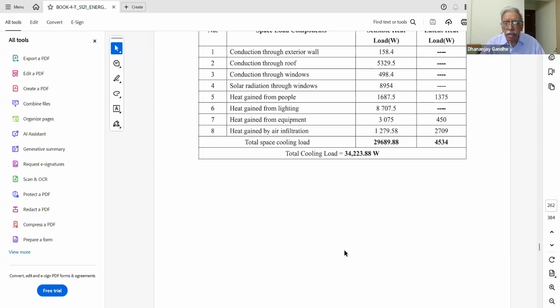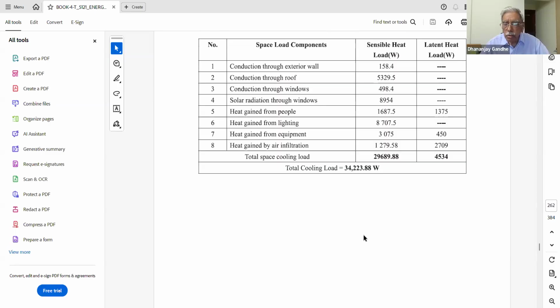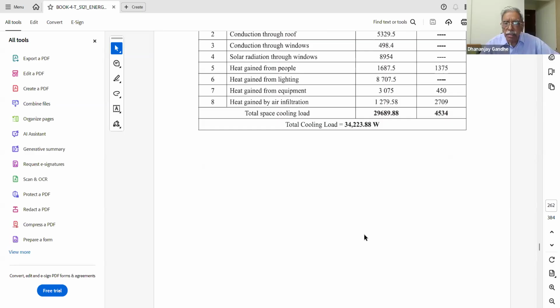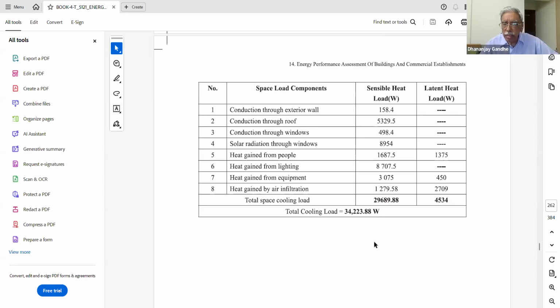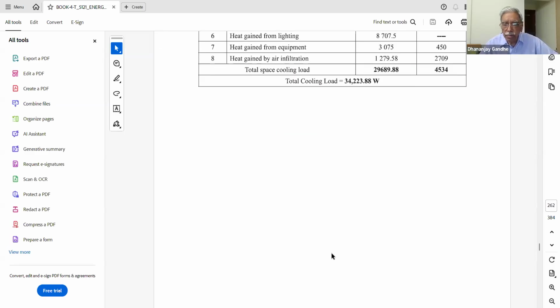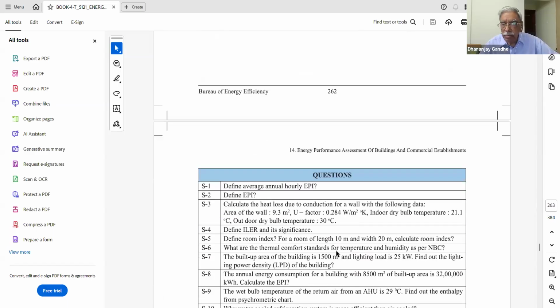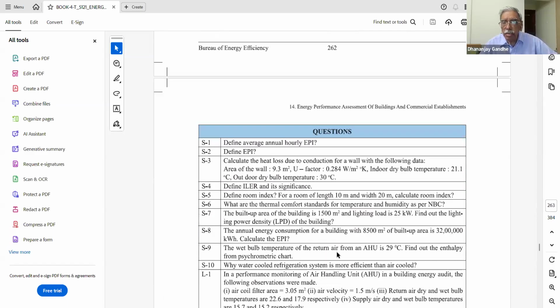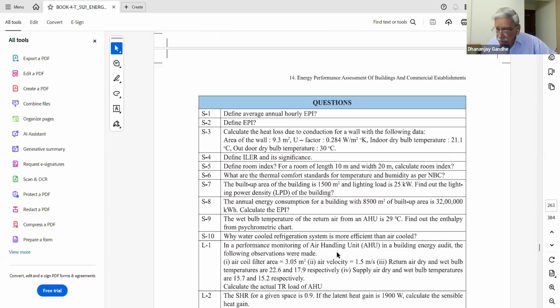For the AC system, you work out the kW per ton of refrigeration and compare with the standard, and also work out the cooling load, to work out the AC performance, and the lighting load. Of course, you have to make measurements and compare with the standard. So this is the theory part of this lecture.